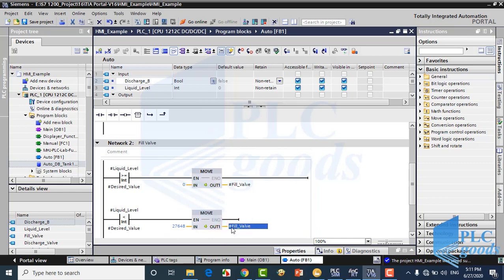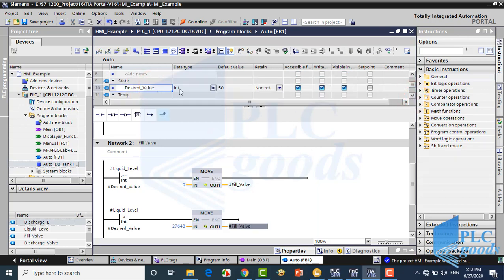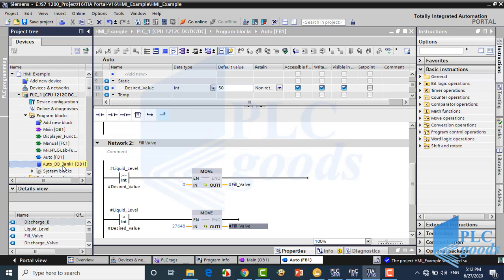The main point is the desired level parameter which has been defined here. Its initial value is 50 percent. This parameter will be stored on the related data block and can be changed by the HMI. This logic can be used for other tanks, but we must use another data block to store the desired level for each tank.